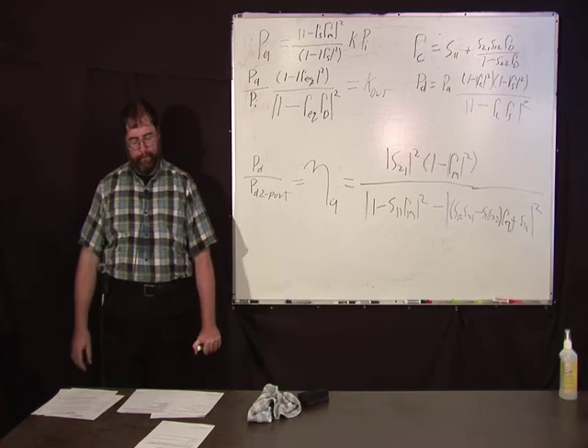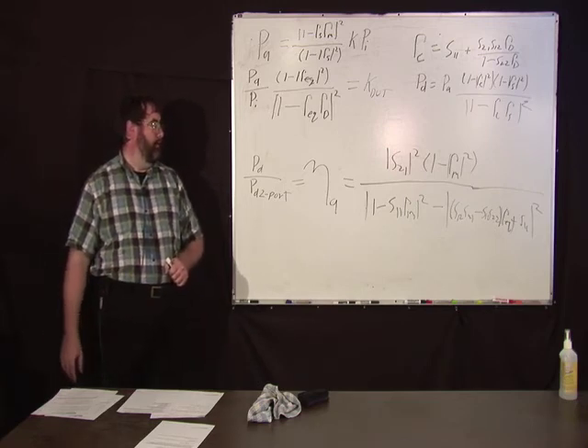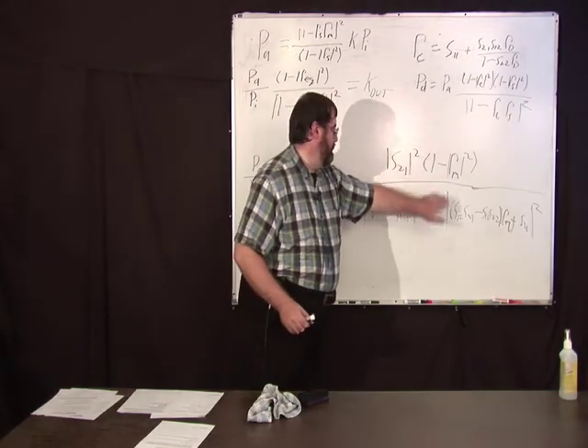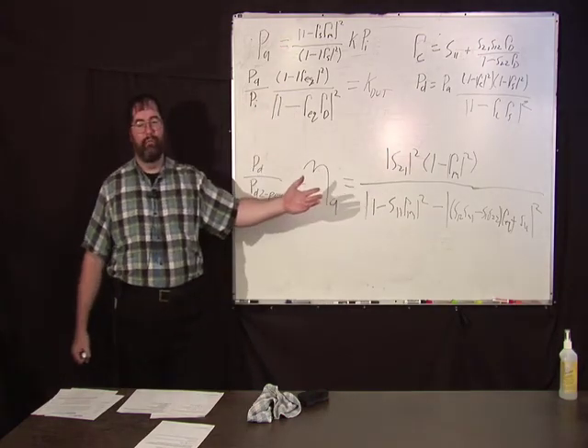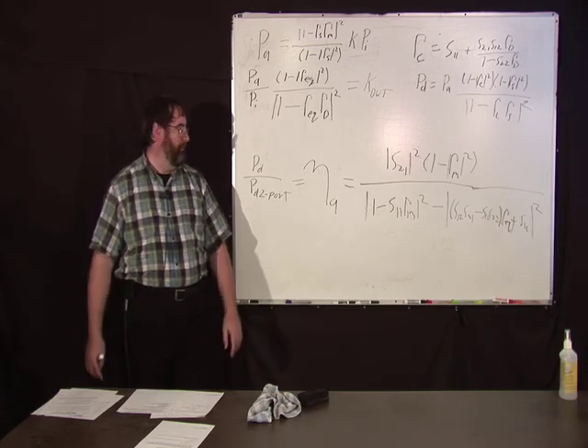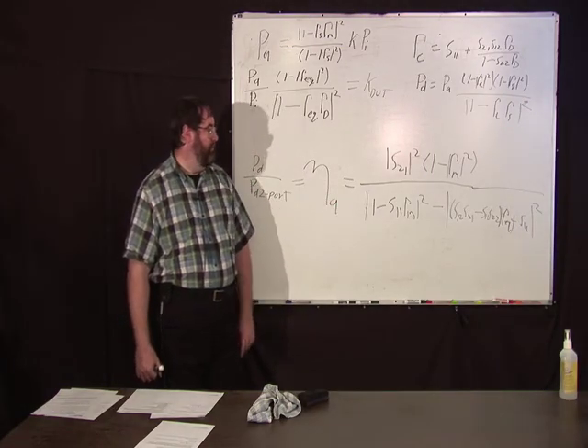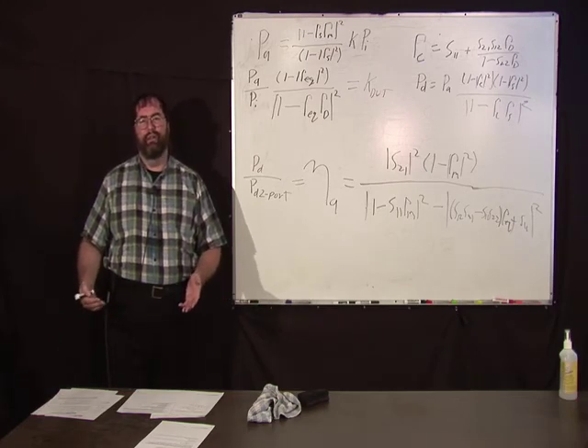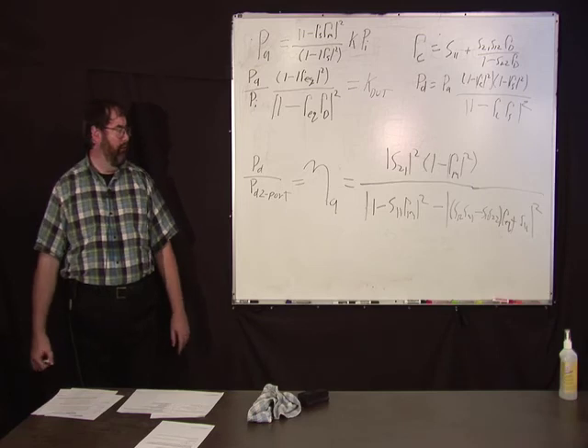And that gives you power delivered to the sensor divided by power delivered to the two port. So essentially all you have to do in the case of calibrating something through a two port is somehow insert this into this equation. Anyway, we've just gone over the primary problem of how you can calibrate power, some of the terms that you can have in a power measurement. I should point out, like this term here, if you assume all these mismatches are zero, all the reflections are zero, all you're left with is this term here, which is not surprising. What that's saying is if you ignore mismatch, if you measure 0 dBm power through a 10 dB attenuator, all that means is you have minus 10 dBm. The rest of this is a correction to that. There's nothing really fancy there, it's just you have to include the mismatch terms, and they can be quite large. A typical power measurement probably has terms on the order of 1 dB. If it's bad reflections, it could be worse.